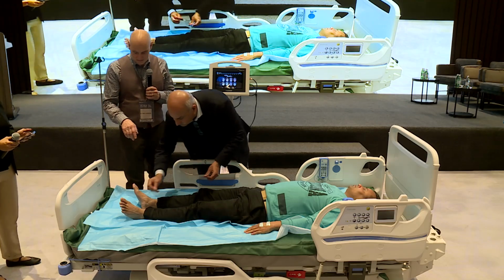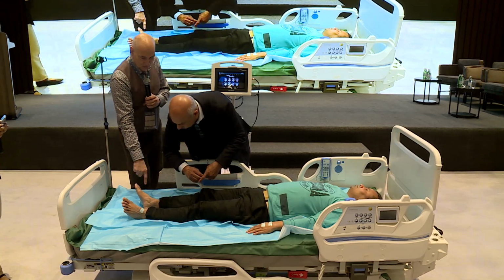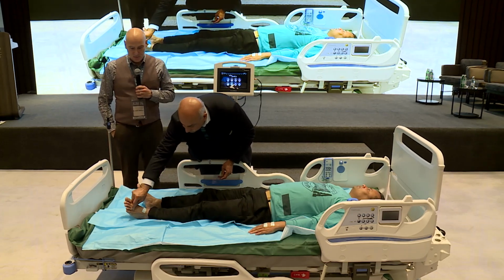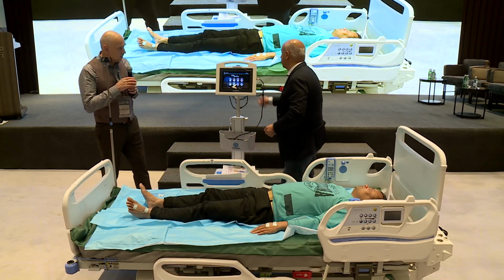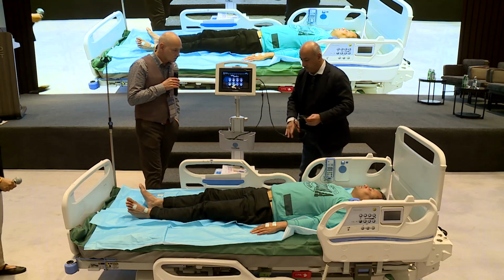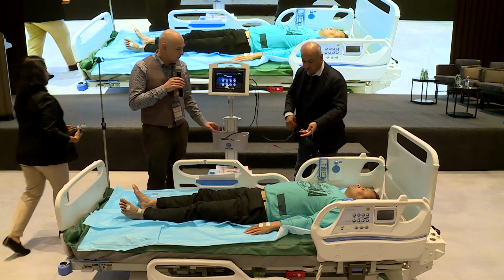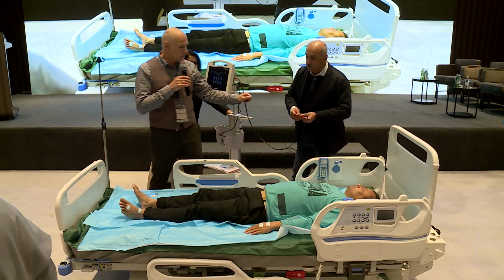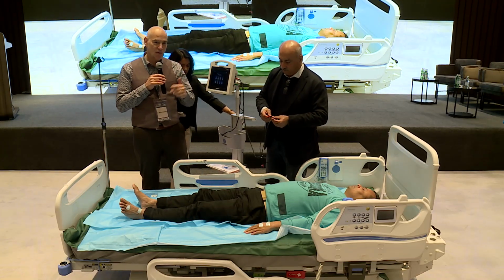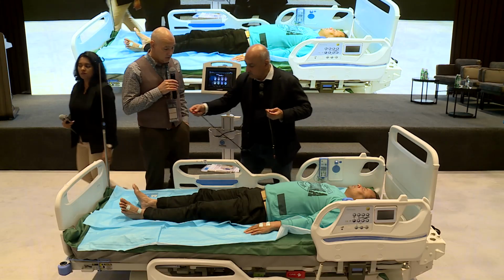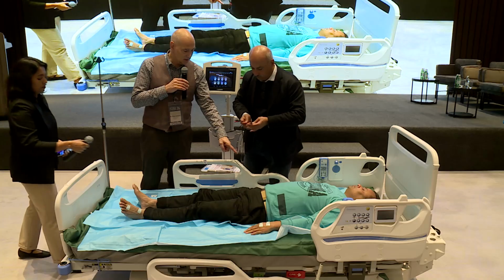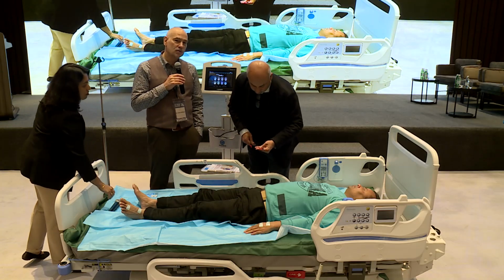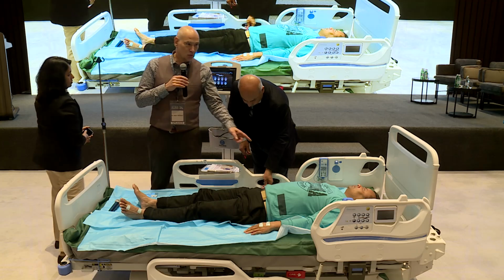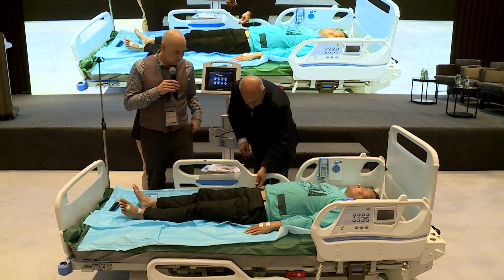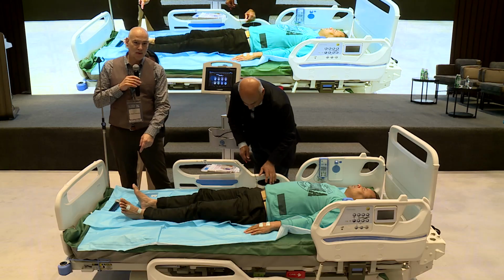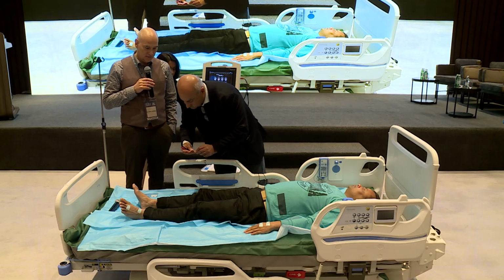So we do the same on the feet, where there is this and just before the toes, and you put them in a straight line. Now we go to the machine. There are 2 cables, one for the left, one for the right, and they have these clips that are numbered 1, 2, 3, 4, 5, 6, 7, 8. So you start, I would say, with the hand, which is 1 and 2, and you put the red on top of the black, 1 and 2. And then you do the same for the right foot, 3 and 4.